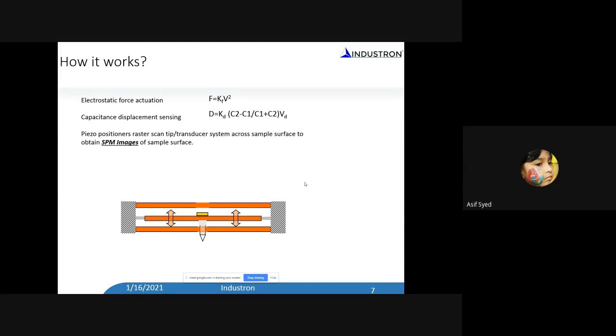So you have this three-plate capacitance structure. The center plate is supported by a spring so that it can move up and down. And these gaps are very small. The gap that we have between these three plates is about 50 to 60 micron. Okay. And now, if you apply a high voltage at the bottom plate, it will generate the electrostatic force, and this center plate will get attracted to the bottom plate. That is how you generate the force.